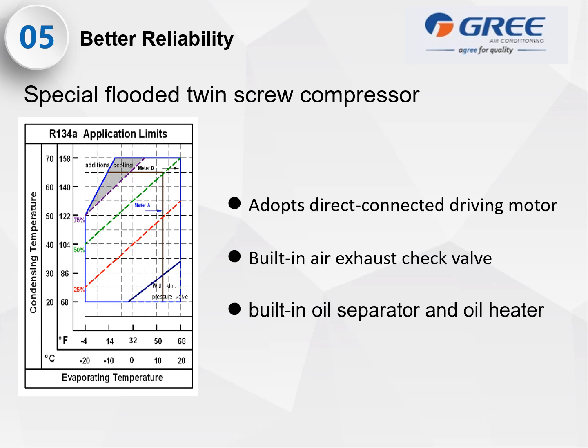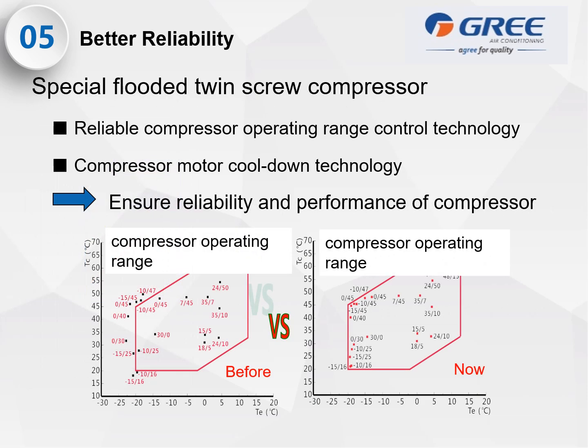Special flooded twin compressor. It adopts direct connected driving motor. It has a built-in air exhaust check valve. It has a built-in oil separator and oil heater. For the special flooded twin compressor, it has a reliable compressor operating range control technology. Compressor motor cool down technology, which is to ensure reliability and performance of compressor. This is the comparison of the previous design and now the current design.